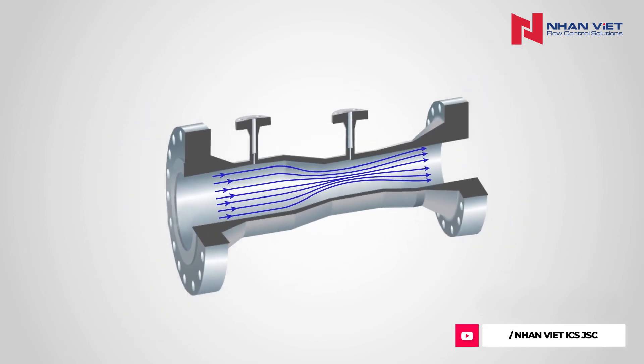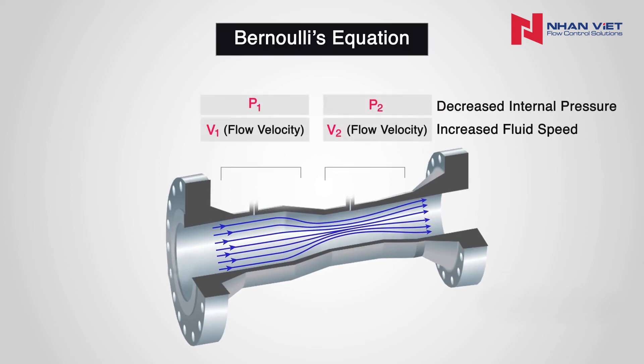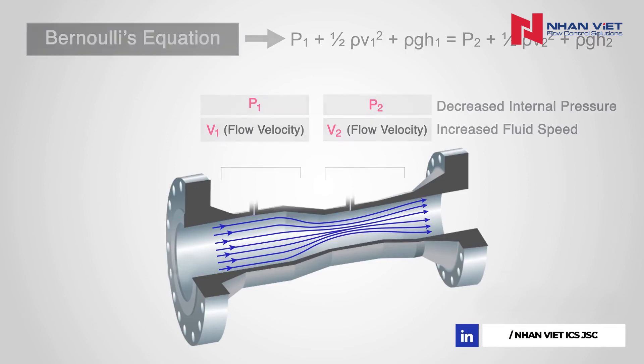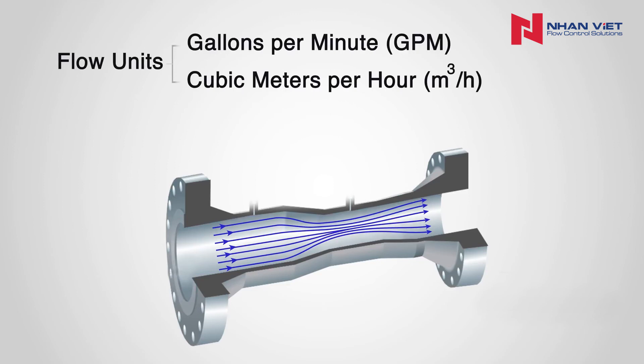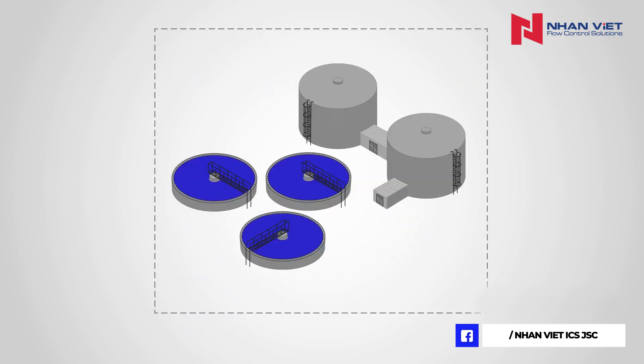These measurements are sent to the electronics housing where the signal processing is done. By using Bernoulli's equation, which states that the pressure drop across the constriction is proportional to the square of the flow rate, the delta P is then converted into units of flow. These units of flow can be gallons per minute or cubic meters per hour. Using DP transmitters to measure flow works best on fluids that are relatively clean and of low viscosity. Delta P flow transmitters support a small span or range, which is why they are very commonly used in water and wastewater applications.